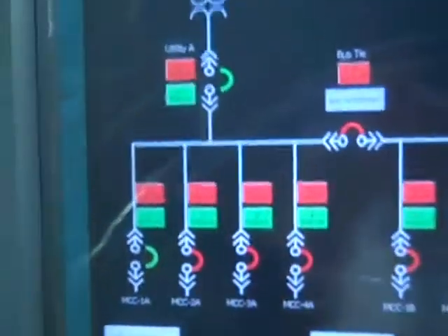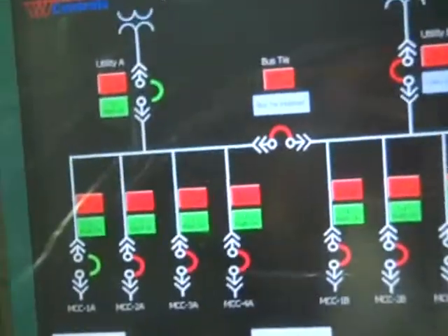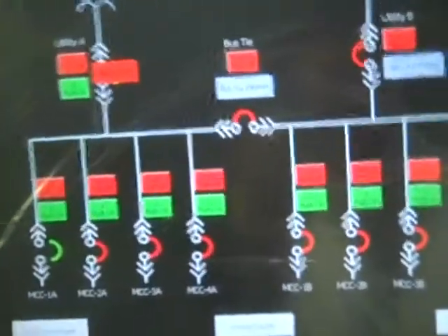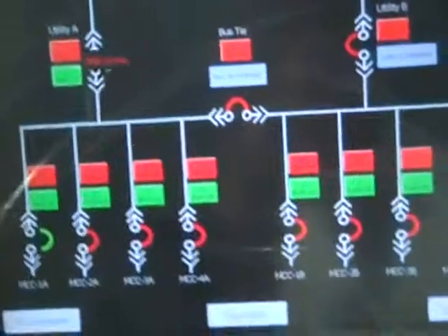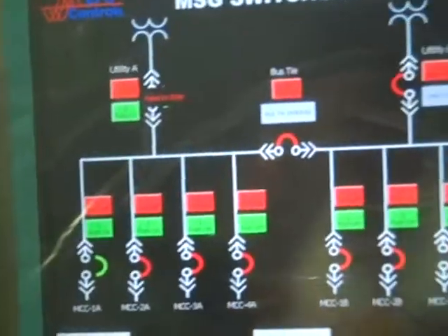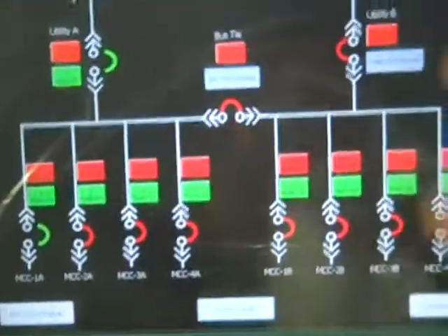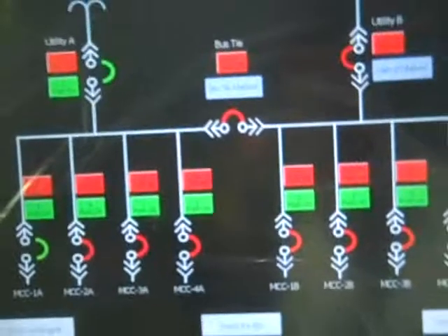If I press for a circuit breaker to close or to open, and it doesn't happen within 10 seconds, we get an alarm, a fail to close, or if it was the other way around, a fail to open alarm. So that's one thing that we just added there. That fault can be reset, and we get back to normal, and can retry however many times you wish.